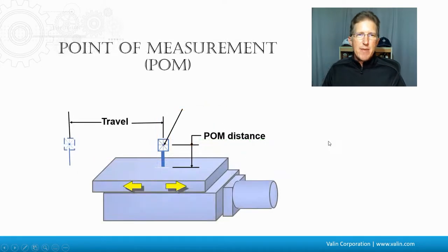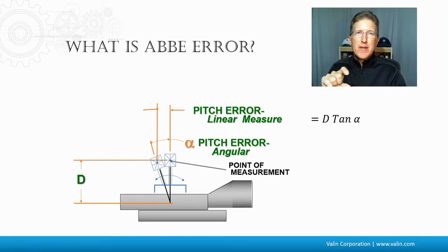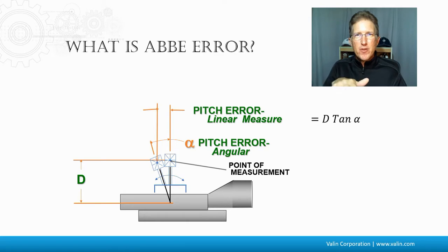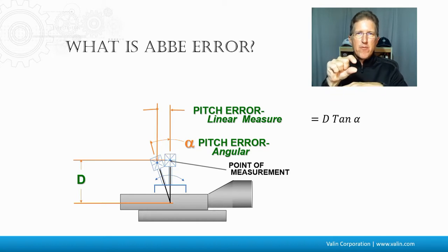What's the Abbe Error? The Abbe Error is the angle that can be caused by the motion of that carriage as it moves down the rails. It could be roll error, it could be pitch error, it could even be yaw error. But each one of those will cause an angular error at that point of measurement that's an inch above the carriage.